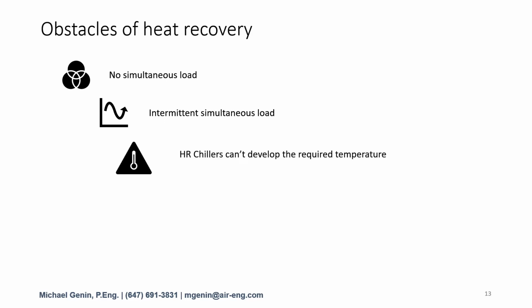Heat recovery chillers can't develop a hot enough water temperature. As heat recovery became popular, chiller manufacturers would adapt comfort cooling chillers and try to force them to do heat recovery. There wasn't much of a mechanical difference between a regular chiller and a heat recovery chiller. Most manufacturers used, for example, R410A as a refrigerant, which is limited to about 120 or 130 degrees in terms of its hot water production. But this is not hot enough for supplementing, especially older buildings with non-condensing gas boilers that need to operate at 160, even 180 degrees. Now, heat recovery chillers are readily available that go up to 160 degrees and in some cases above 170 degrees.